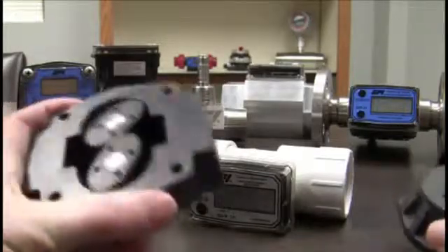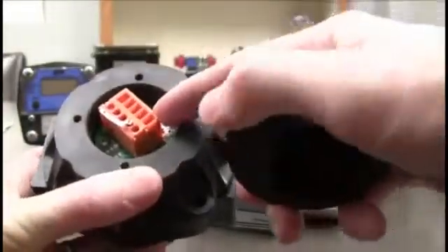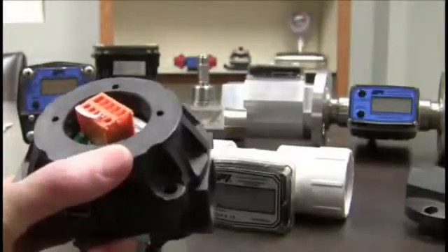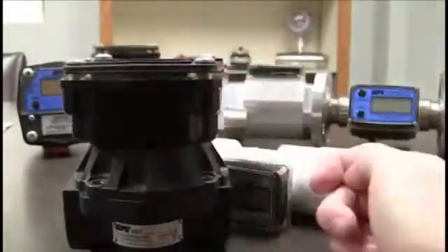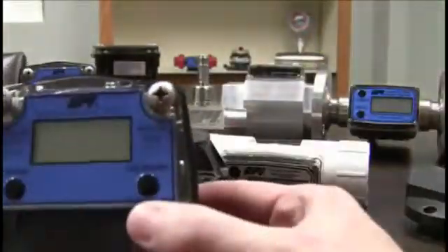Now our oval gear meters, like I said, here you're showing one that's just going to be a pulse out only, where the wires go straight into that reed switch I was talking about. But you can also get it with a display. So it's going to look just like that. The display can sit on top, just a regular GPI display. And it's going to do the same thing. It's going to count those pulses. The display knows exactly how many pulses equals a gallon, just the exact same way the turbine meter does. And so then you can see what you've got on there.